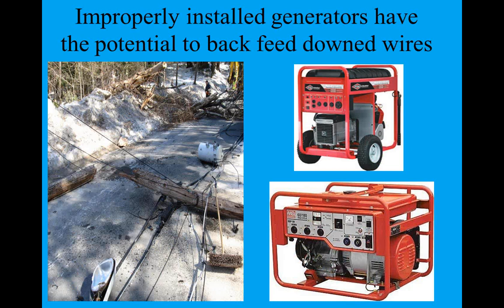Now, you can look down the street. You can see down here that I had a tree that came down, and it's got people trying to start to do some cleanup, and I got a broken pole down here. I got a transformer on the ground. Now, I need you to think about this. If you have a generator, there's only two ways to use this thing safely. You either run a bunch of extension cords and run everything off an extension cord directly off your generator, or you use a 240 plug through a code-approved disconnect switch that is going to prevent you from backfeeding into the grid.